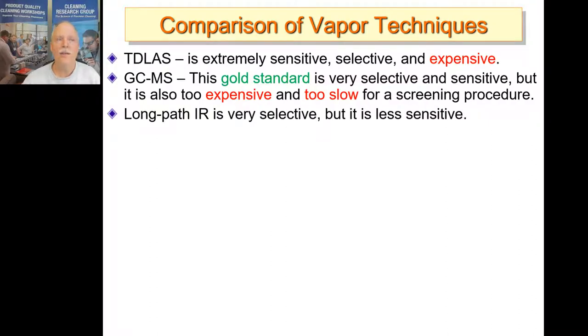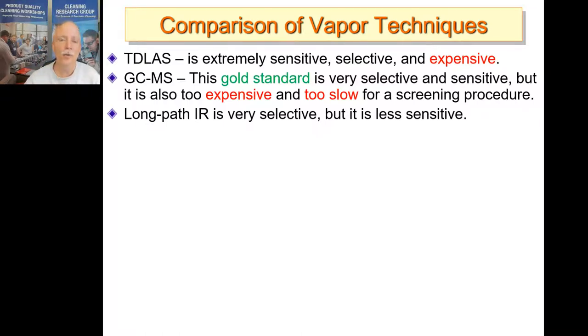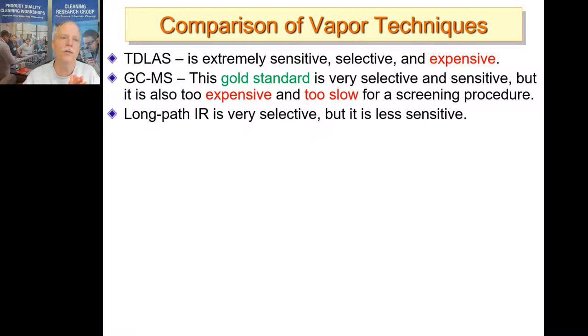Long path IR is very selective but also less sensitive. You take an infrared beam and bounce it between two mirrors for a very long path — some have 90 to 100 reflections, achieving path lengths of around 10 meters — but it's still pretty slow and not very sensitive.